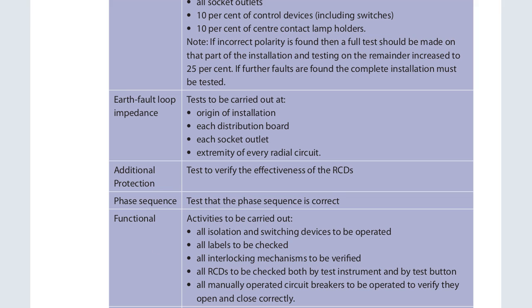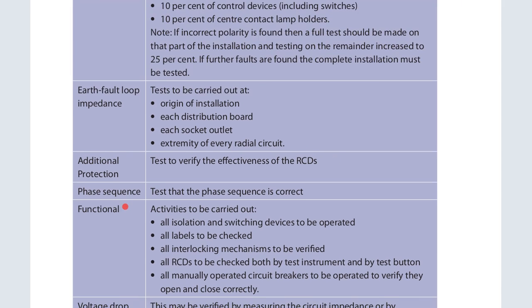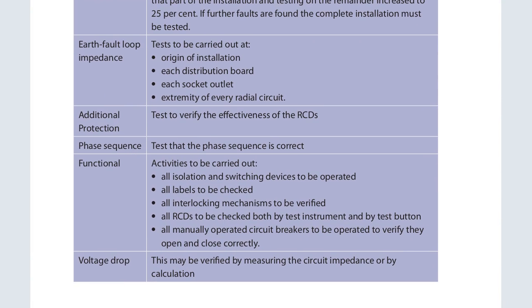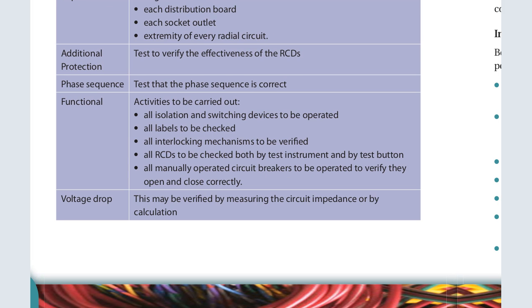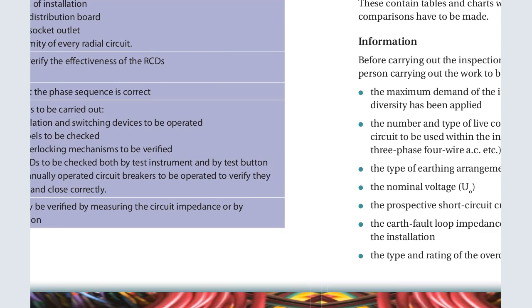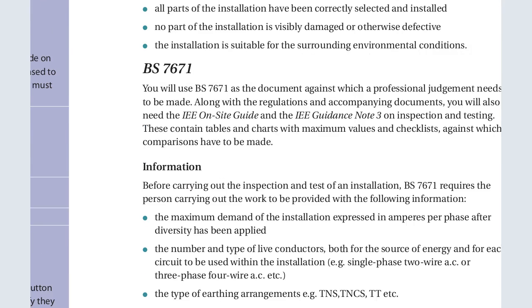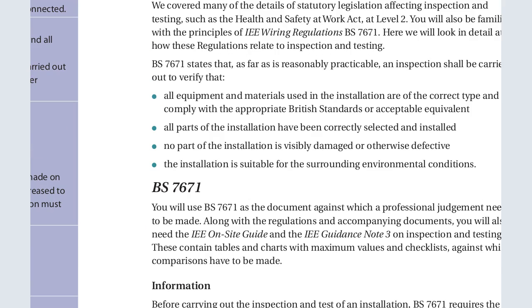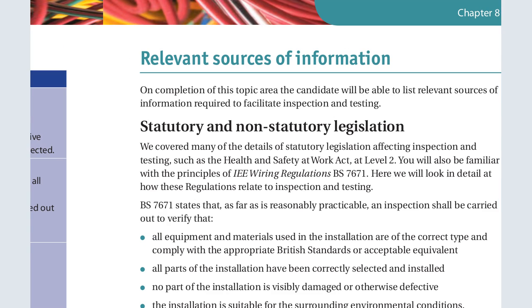All labels are checked. Interlocking mechanisms are also verified. All the RCDs are to be checked, both the test instruments and the test buttons. Also, we check that all manually operated circuit breakers are operated. And also we check that the voltage drops may be verified to measure the circuit impedance. And then as well, you can see now the standard is here and it is quoted.